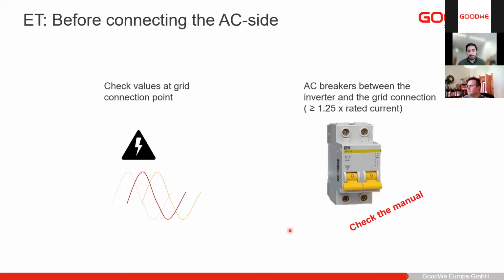Before connecting the AC side, you need to check the values at the grid connection point. Here you can use the multimeter to check that it has the proper voltage values and so on. Always make sure that you install proper AC breakers. Here you have only a 2-pole, but according to the country standard, as it's a 3-phase inverter, you will need to have a 3 or 4-pole AC breaker.